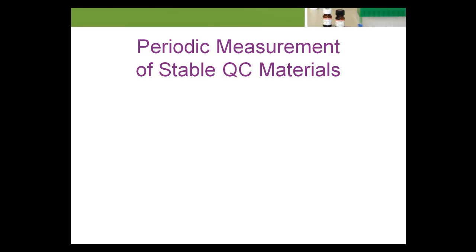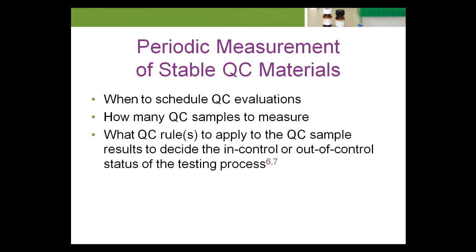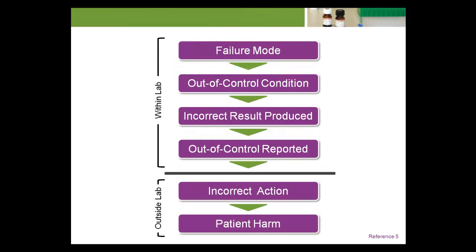Defining a QC strategy based on the periodic measurement of stable QC materials involves answering three questions: number one, when to schedule QC evaluations; number two, how many QC samples to measure; and number three, what QC rules to apply to the QC sample results to decide the in-control or out-of-control status of the testing process. Given the answers to these questions, the performance characteristics of the QC strategy can be quantitatively assessed. The outcome metric that best fits into the overall model is the expected number of incorrect patient results produced and reported due to an out-of-control condition of a given type and magnitude.